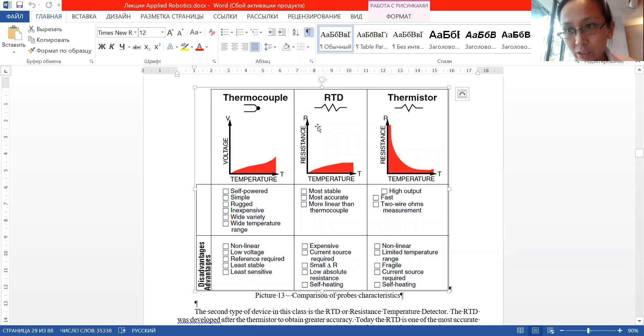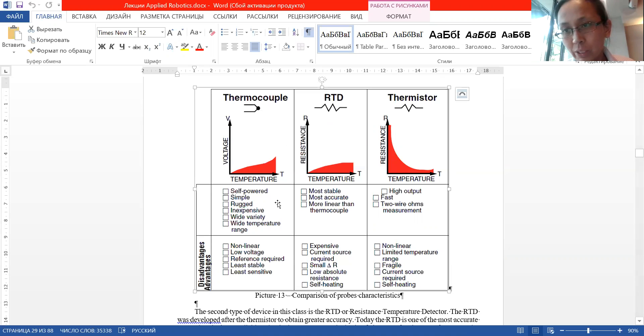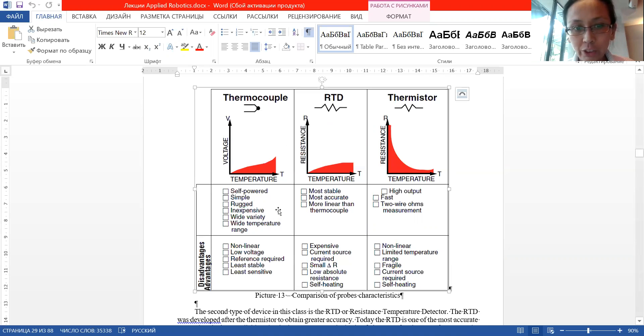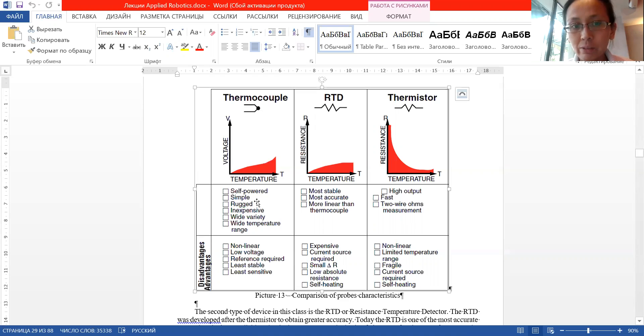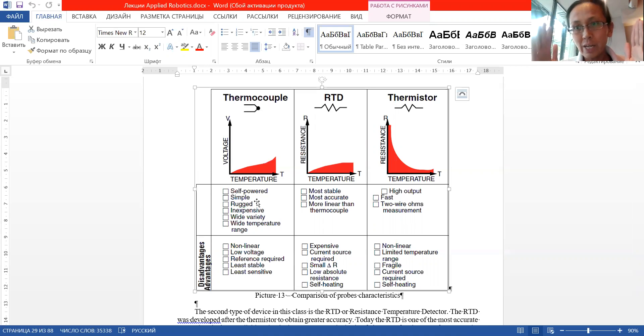If you need a linear signal, it's better to use RTD. But if you can convert the nonlinearity using some device or programming, then thermistors are okay. As for the advantages of each type: thermocouples are self-powered — they can work by themselves because they generate voltage. They are also simple, rugged, inexpensive, available in wide varieties, and have a wide temperature range.